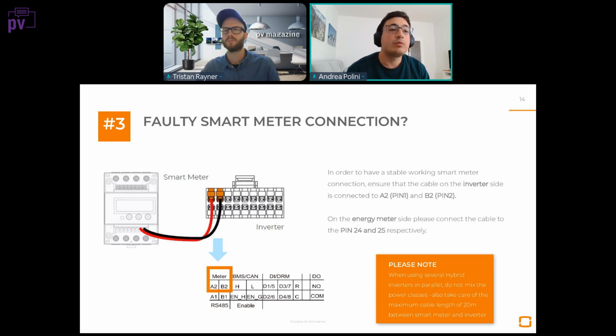And for the normal PV inverter, the first thing I would say is that you need to be careful to buy a Sungrow energy meter. We are cooperating with different brands like Acrel and Chint to make the meter for our inverters. However, we are making a special version of this energy meter for Sungrow inverters. So the installer must buy the Sungrow branded Acrel or Chint meter. Other meters off the shelf will not work with our Sungrow inverters. So this is quite important and has happened several times that people bought off the shelf a Chint meter, for example, or a meter from another brand, and they have tried to connect it with our inverter without success.